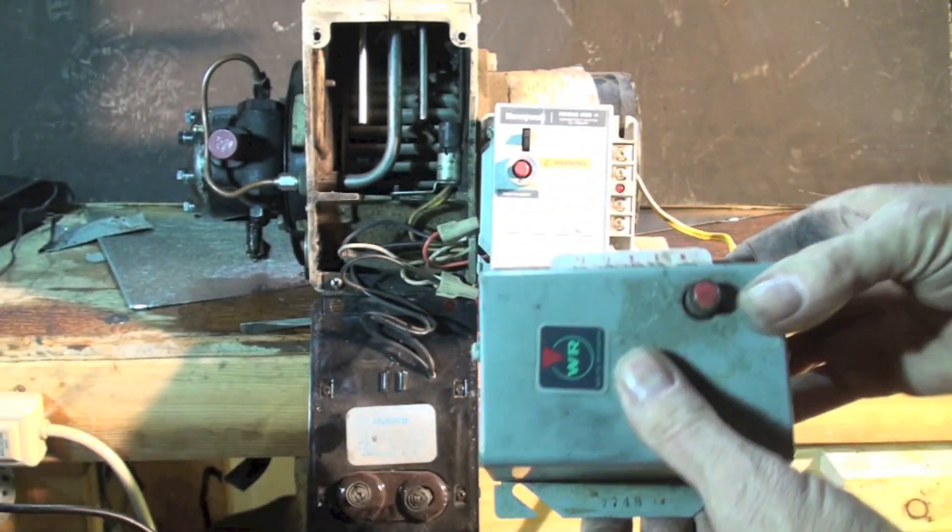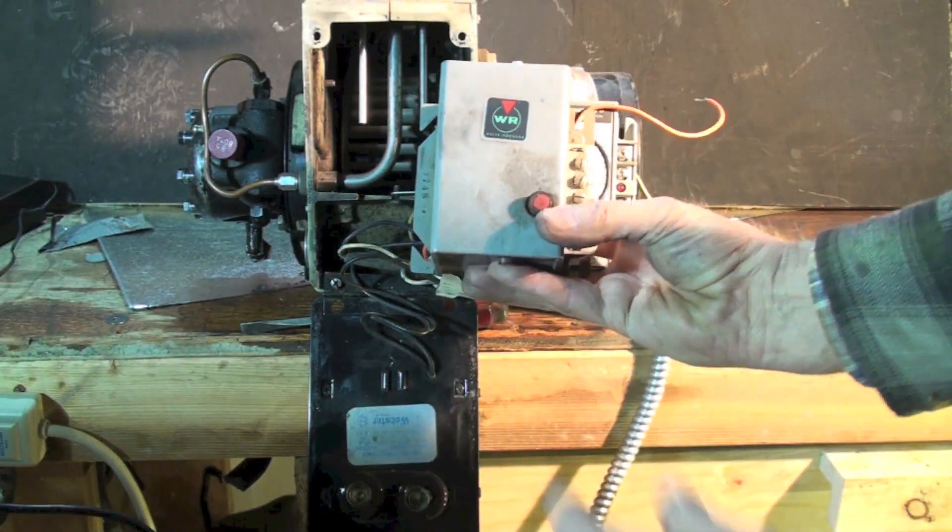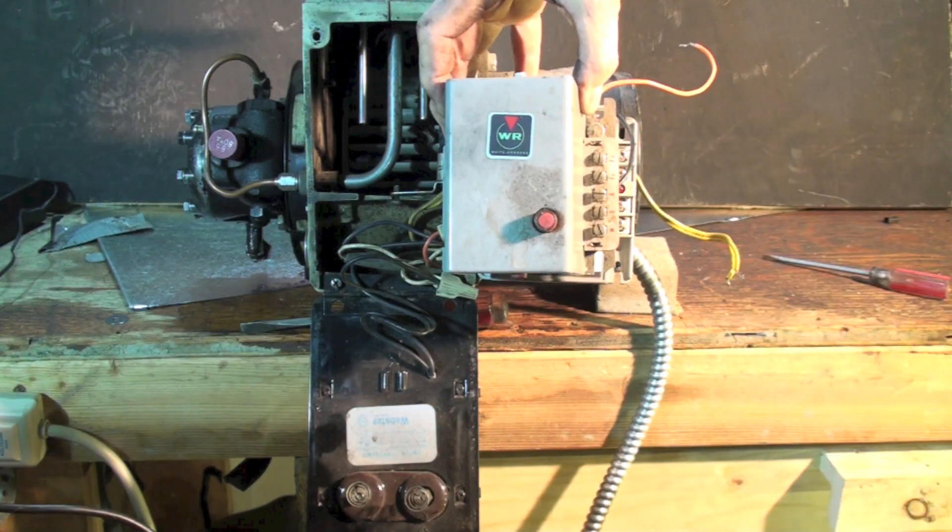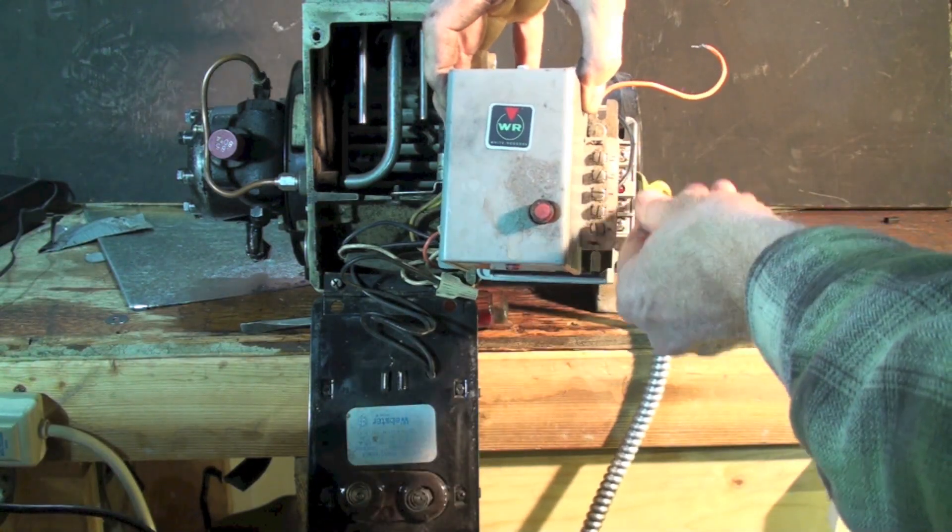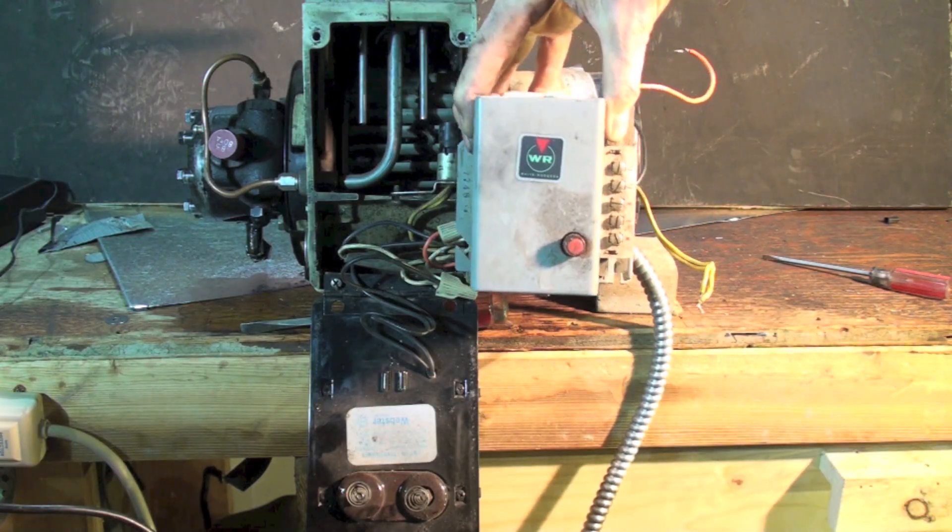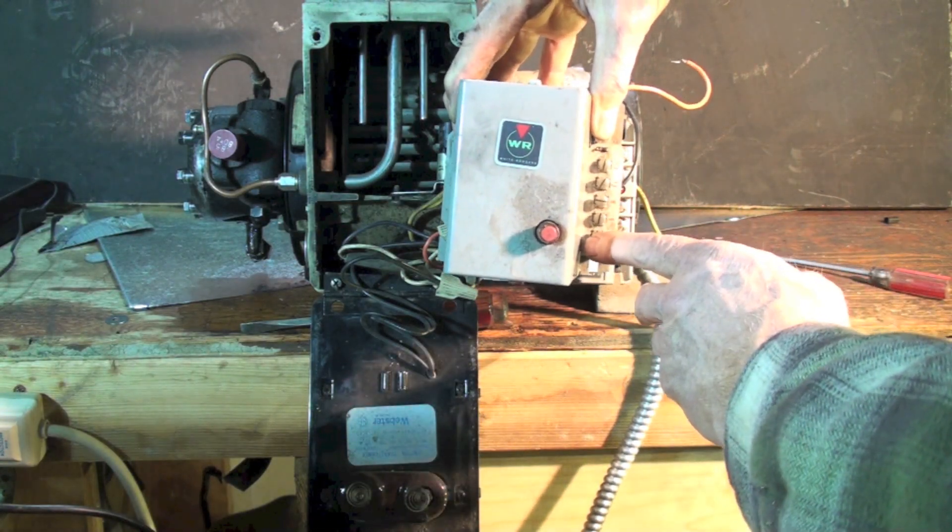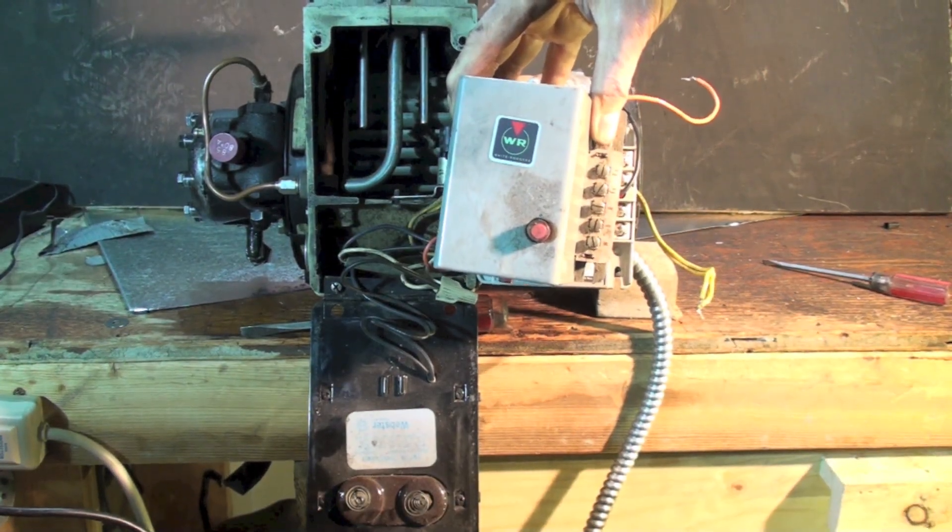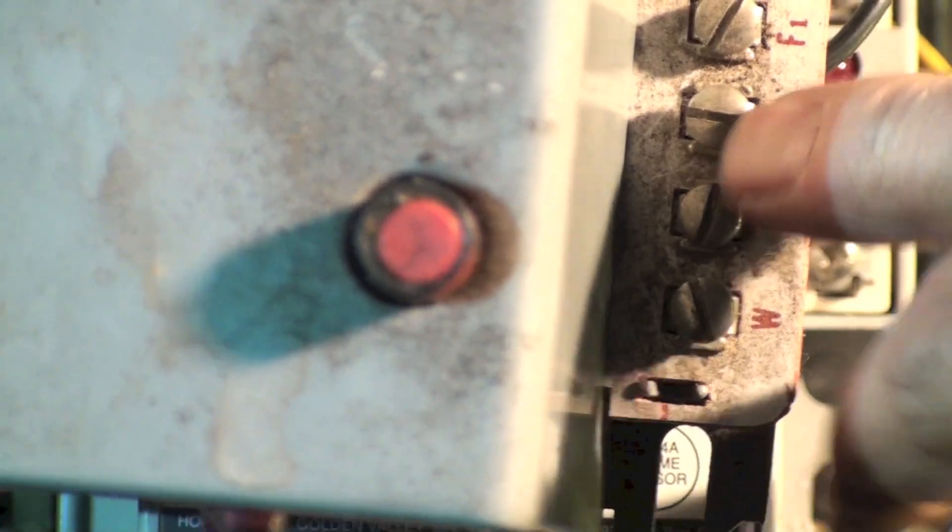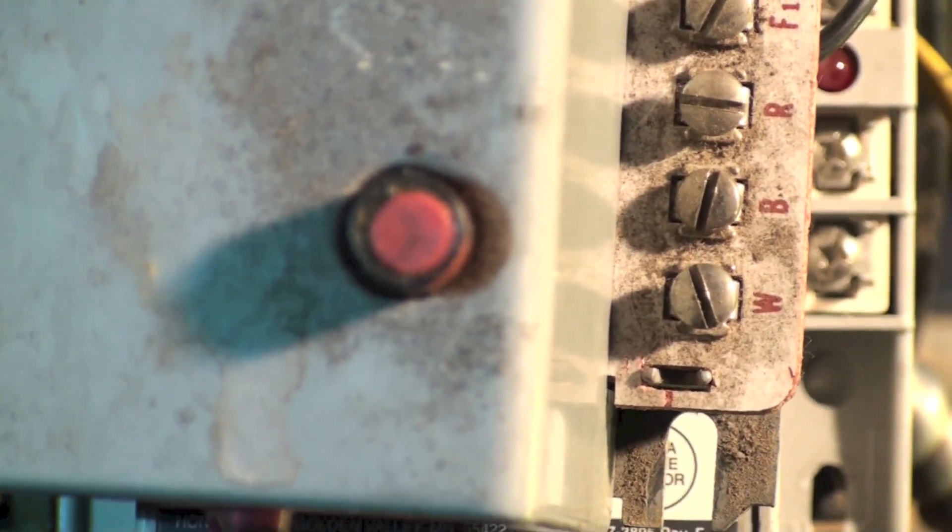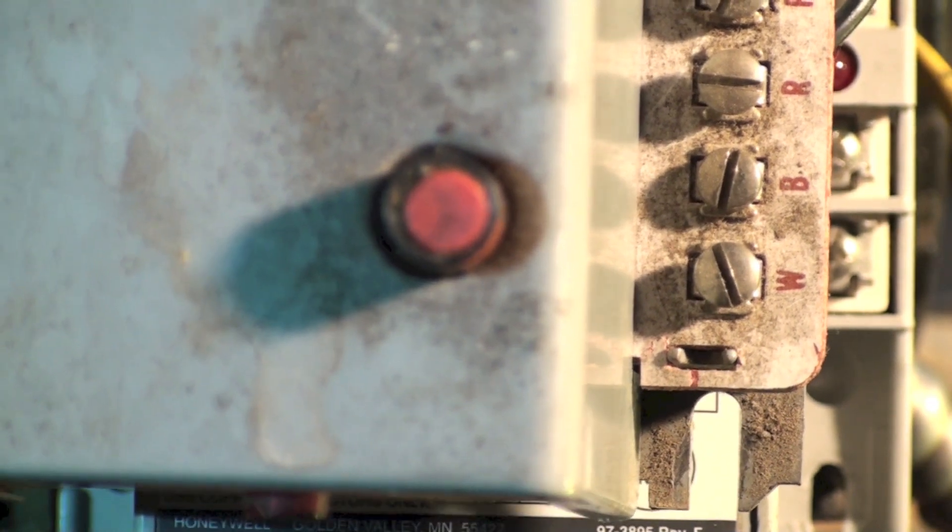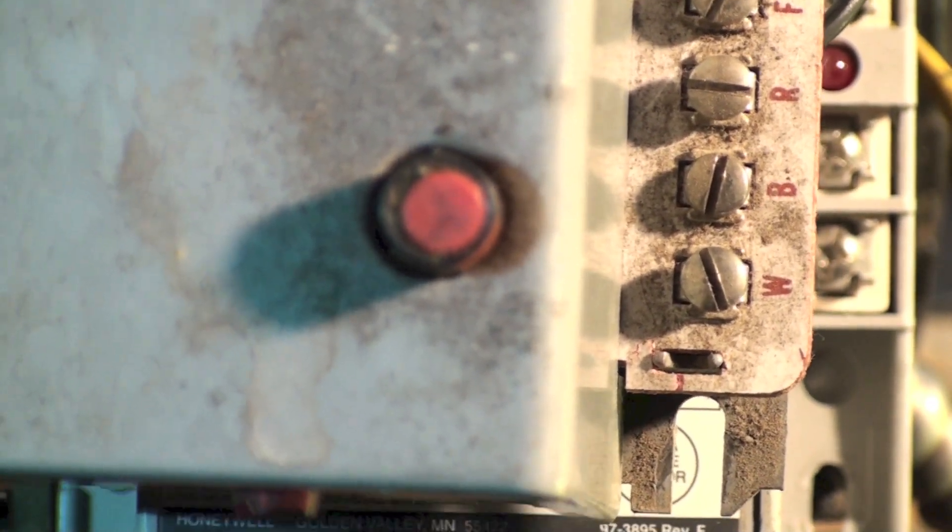The only other difference with this control is, if you notice, I have F1 and F2. Now that's for these yellow wires right here that's going to the flame sense. I have a W, a B, and an R. Let me get a little closer on that so you can see. There's your W, B, and R. That's for a three-wire thermostat. Let's not get into three-wire thermostats today. Let's just deal with a two-wire.